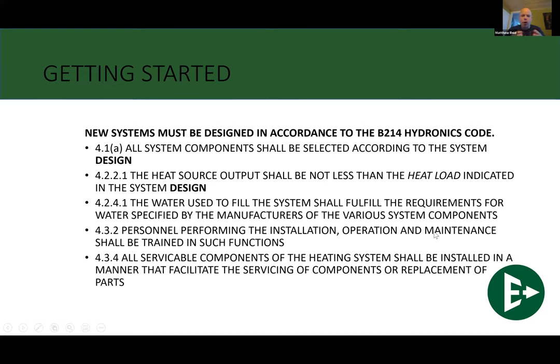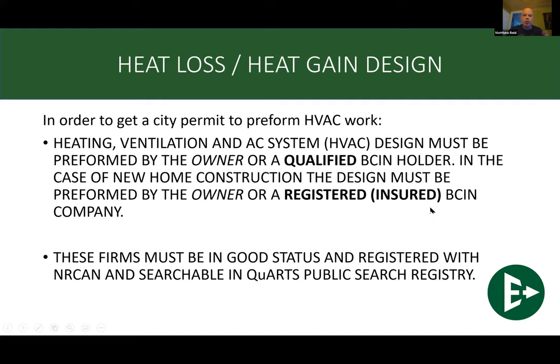Okay. All serviceable components of the heating system shall be installed in a manner to facilitate the servicing. So what I mean by this, ball valves and unions, you cannot possibly have enough of them. You can't have too many of these things by any means. You should be able to take this whole system apart if you need to. Just because you don't think you're ever going to be servicing maybe a dirt separator or something like that does not mean that it's going to cost you a tremendous amount of money to throw a ball valve and a union in there. Don't be afraid of them. They don't add too much to the job, and by the time you get it all done, you're going to thank yourself for making sure that these parts are serviceable. You can get in there and do these changes and cleaning up that you're looking for.